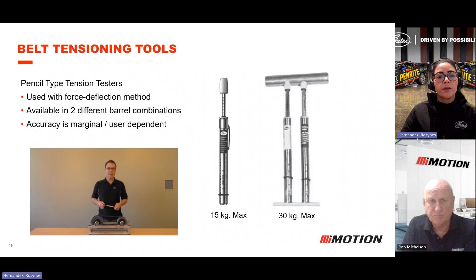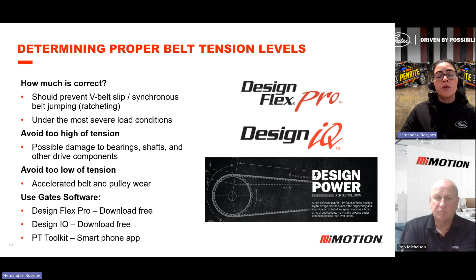As I mentioned, how much is correct? This is where you can look at the program. You run the calculation based on your RPMs, your pulley sizes and belt length, and then you will have the tension that you need to apply to that drive. You need to know that every belt drive has a unique tension. In the past there was a general rule, like if it's a belt A, B, or C, but I encourage everyone to go into the program and put in your belt parameters, and then it gives you a more accurate tension to apply.